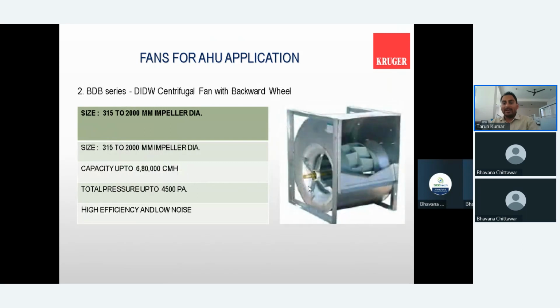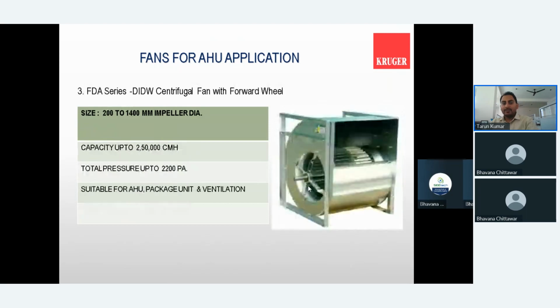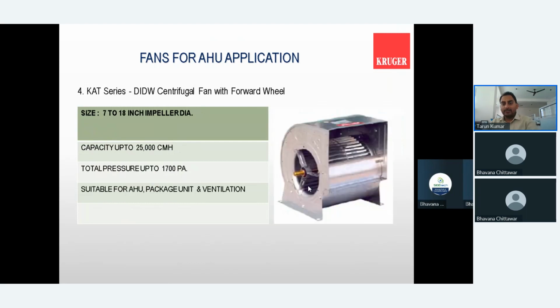The backward curve fan, as I told, is very similar to the aerofoil curve. It has a little bit lesser efficiency than the aerofoil curve, and it is used for all similar applications where we use the aerofoil curve impeller. Further to that, wherever our static pressure is less than 50 mm static, we are supposed to go with the forward curve fan for all kinds of AHU application.